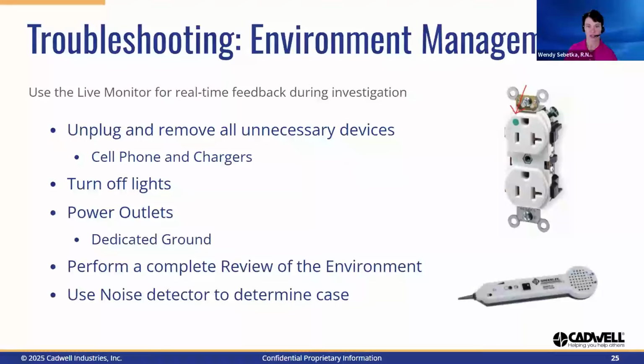Switching outlets, especially to one with a dedicated ground, should be trialed. If you're not familiar with how to locate a dedicated ground outlet, they are usually distinguishable by the red outlets, an orange triangle, or a green dot on the outlet as shown in the image on the slide. If a complete review of the environment is not successful in determining the cause, the use of a noise detect probe may assist you in locating the source. Obtaining a noise detect probe is preferred, but if one is not readily available, you can download an EMF detector app on your phone for quick access.